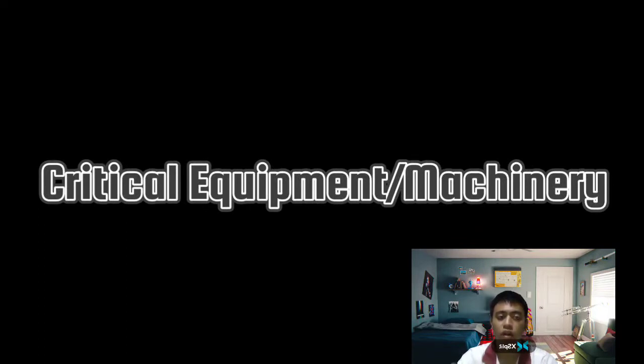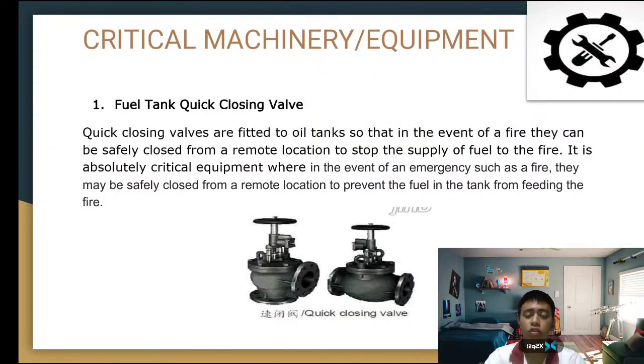So the first equipment is the fuel tank quick closing valve. Quick closing valves are fitted to oil tanks so that in the event of fire they can be safely closed from a remote location to stop the supply of fuel to the fire. So it is absolutely critical equipment, where in the event of an emergency such as a fire, they may be safely closed from a remote location to prevent the fuel in the tank from feeding the fire.